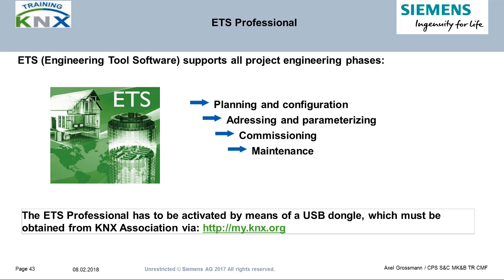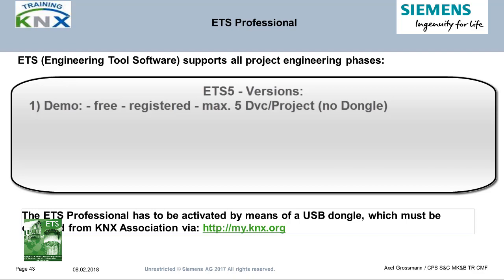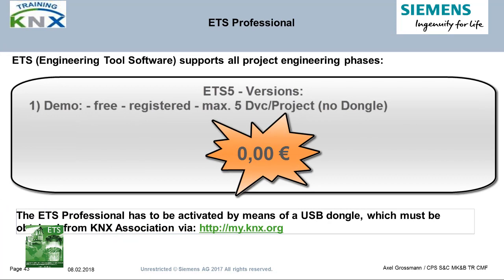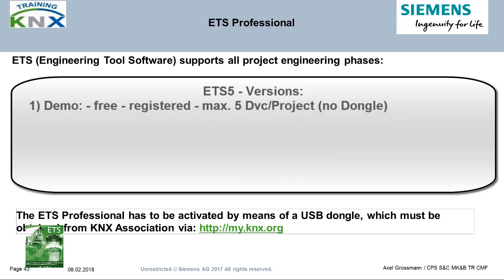As already stated in the chapter General Information, ETS is the only comprehensively usable tool for all KNX plans, beginning with project design until maintenance and repair in later states of the building operations. The current ETS version is 5.6.4 as of June 2018 and is available in 4 different editions. 1. Demo version can be downloaded for free after registration in the my.knx online portal. It is about 120 MB large. This is actually the full version, however, it is limited to only 5 bus devices in one project, cannot operate any apps or plugins, and cannot be updated since it is not licensed.